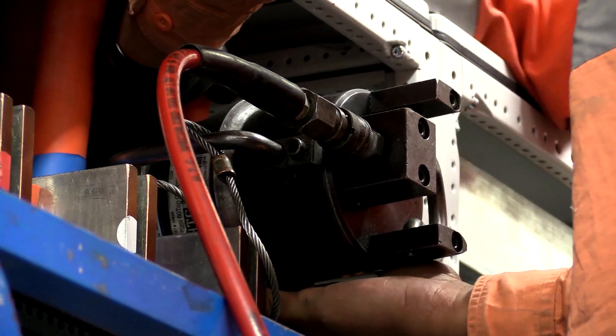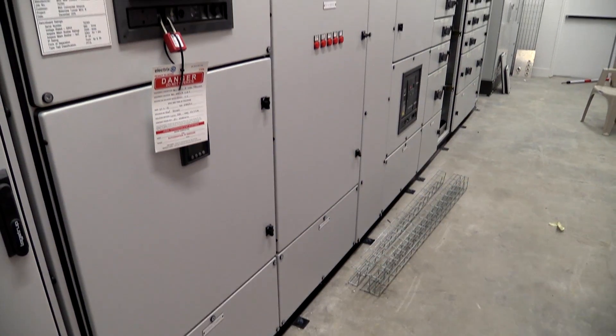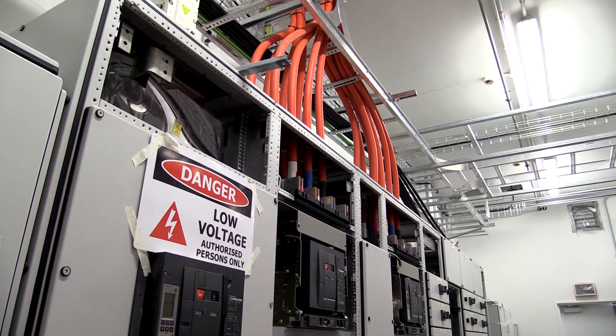So we have two power stations supplying each end of the tunnel. If we lose part of Auckland, a different part of Auckland will still supply the tunnel. We also have a link between the northern and southern buildings connecting that 22 kV supply through both tunnels, so we would effectively have to lose two power stations in Auckland to lose power at this building.